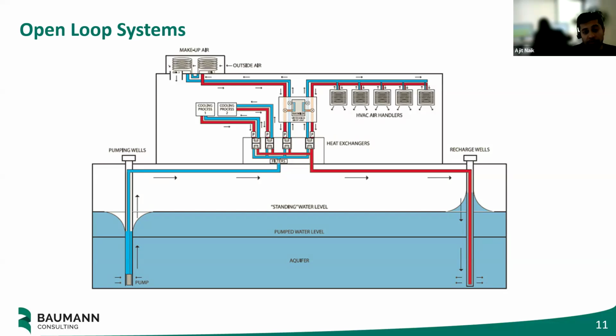You got to be real careful with water chemistry - it can change, it can corrode your pipes, it can corrode your materials, it can lower the lifespan of your heat pump. Those of you who've worked with cooling towers know water chemistry is really important there, usually for health and safety reasons, but it's not any different here. Ultimately, you need to make sure your chemistry is balanced to avoid adverse outcomes that can impact your building's longevity and also have environmental impact - we don't want to be returning dirty crud back into Mother Nature. So these systems exist and are common in some parts of the country, but this isn't really a thing in DC or the DMV more broadly.